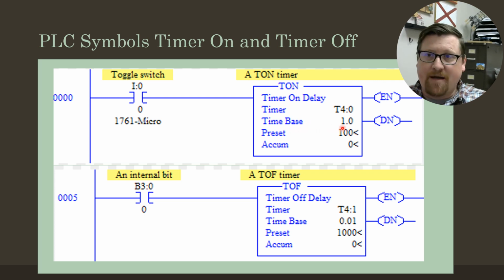It's going to have several different time bases, right? This timer is limited by how many pieces of information it can handle in a certain amount of time. The PLCs that we use in our lab, the SLC 500s, that number is 32,756 or something like that. And so it can only count to 32,756. If you're counting by ones, that's a lot of time.